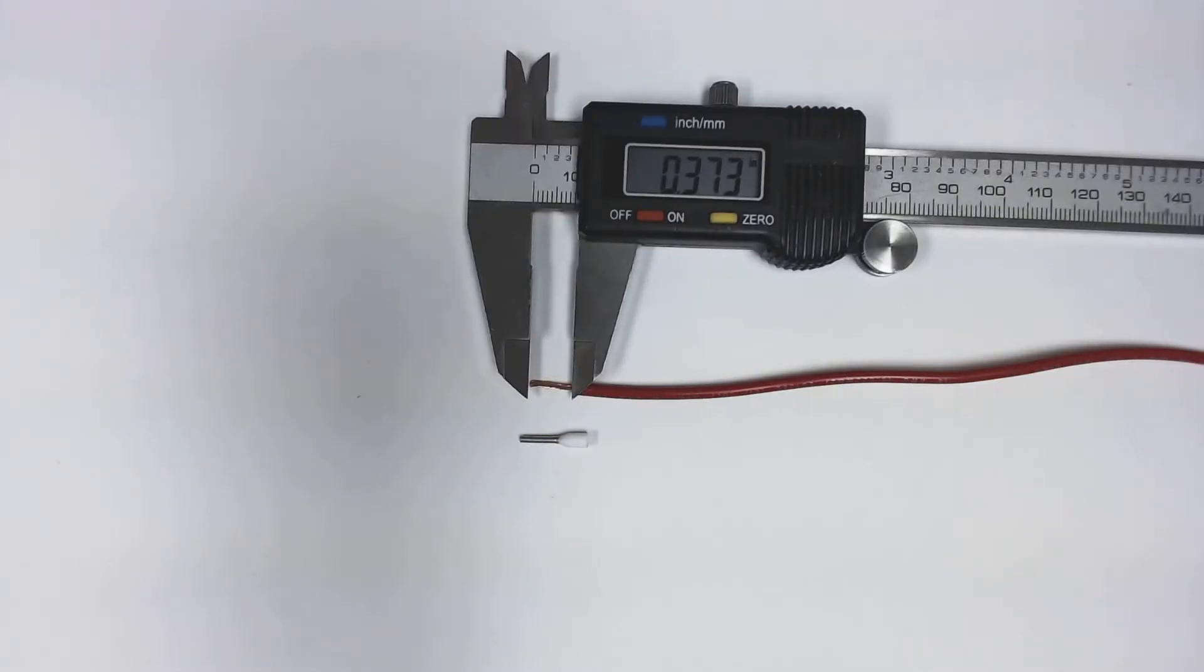The wire must be stripped back to the proper length before insertion into the ferrule. We recommend a strip length of 3 eighths of an inch, or .375. This translates to about 9.5 millimeters.